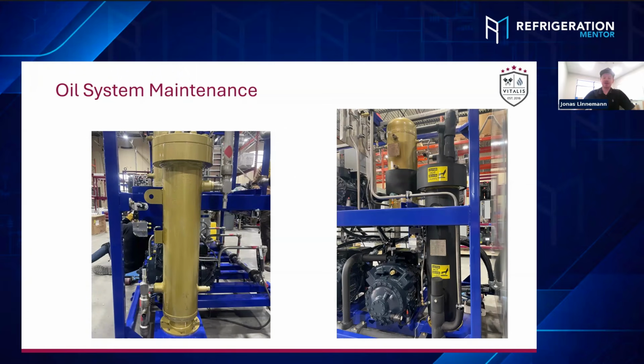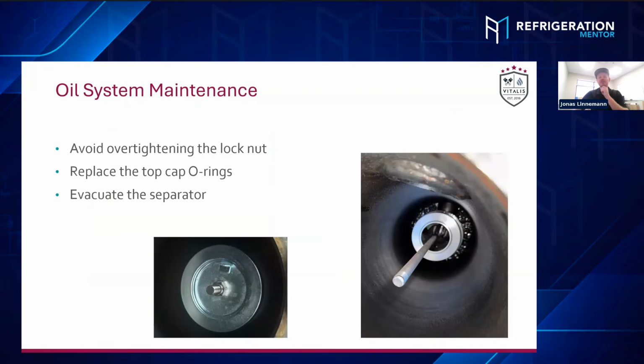So that it's safe. I've also put this picture in here because here you can clearly see the remaining oil at the bottom of the oil separator. And you can see that it's basically just boiling like water. That's just the CO2 gas dissolved inside the hot oil, and with draining the pressure, it all bubbles out. And that takes minutes. So it's good to drain that oil before opening through that oil return valve into the oil reservoir.